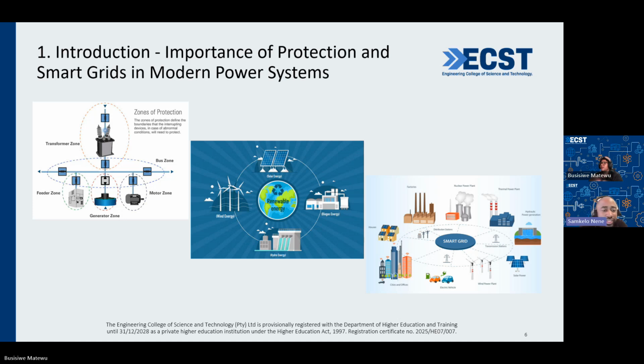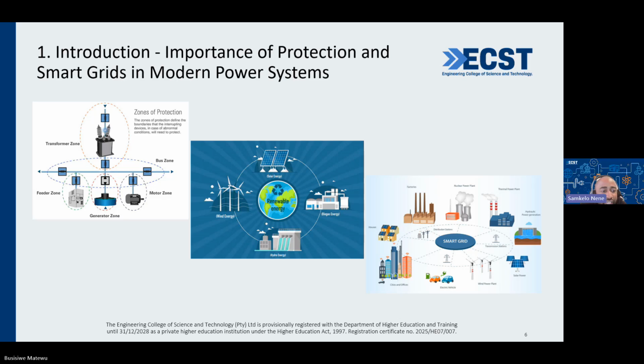If you look at those dotted lines, you see there's one around the transformer, there's one around the feeder, the whole line, there's one around that generator zone, there's a motor zone. So those are zones of protection. Each zone, or each circle, will have a protective system - a protective relay, a circuit breaker, which is supposed to respond when there is a fault within the respective zone of protection. So for example, if there is a fault in the transformer zone of protection, then the circuit breaker and the relay that is within the zone is supposed to act first as primary protection.